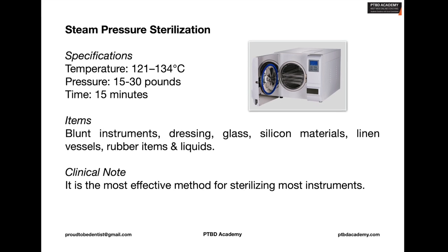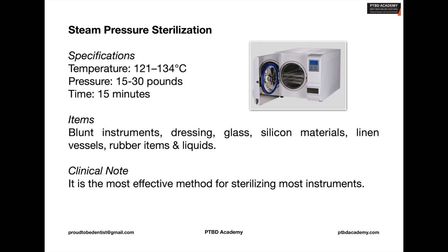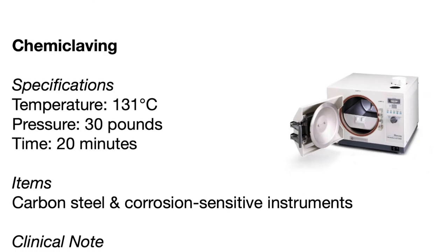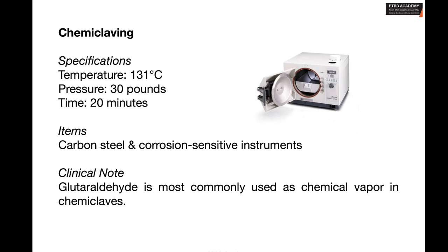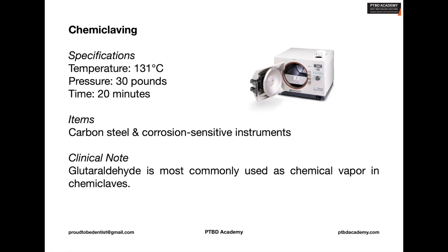Steam pressure sterilization operates at 15 to 30 pounds of pressure for a duration of 15 minutes. It's considered the most effective method for sterilizing most instruments including blunt instruments, dressings, glass material, silicone materials, rubber items, linen, vessels, and liquids. Now coming to chemiclave — chemical vapor under pressure at 131 degrees centigrade at 30 pounds is used, and carbon steel and corrosion-sensitive instruments can be sterilized without rusting, so that's the advantage of chemiclave.